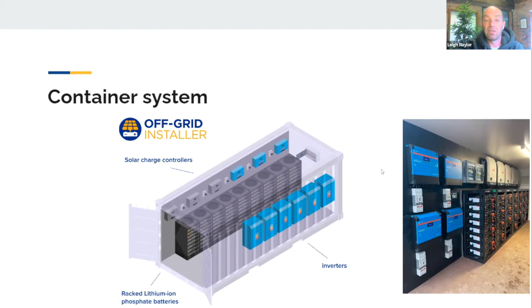So again, those are the rack mounted batteries there. Above those are the DC to AC inverters, and to the left of those are the DC to DC solar charge controllers, commonly known as MPPT, which stands for maximum power point trackers. They track the maximum power point on the solar panels and operate to convert the best available solar power from the panels straight into your batteries.